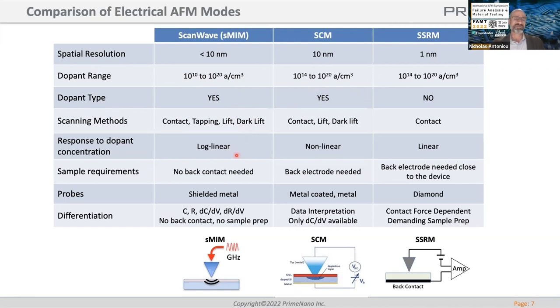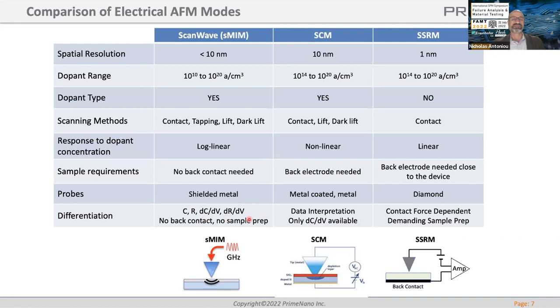An important thing is that the response of the signal to dopant levels is log-linear, making quantification easy. There's no complicated algorithm — you use a reference sample and do quantification of dopants. We're also doing that for dielectric constant. Because we use microwaves, we don't have to send a current through the sample or have a grounded sample. We can look at an exposed dielectric or a sample sitting on a dielectric — no real sample prep requirements other than exposing the area you want to see.